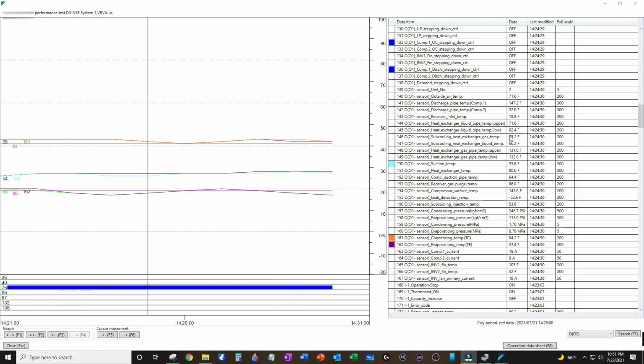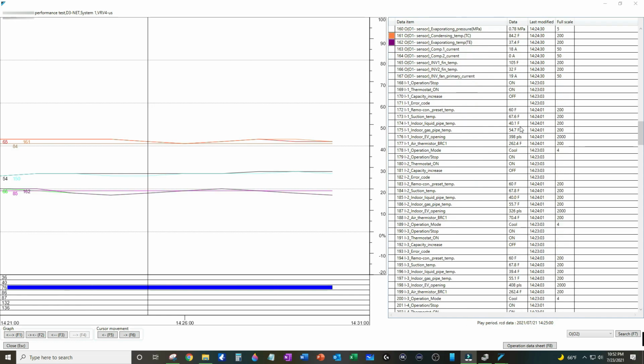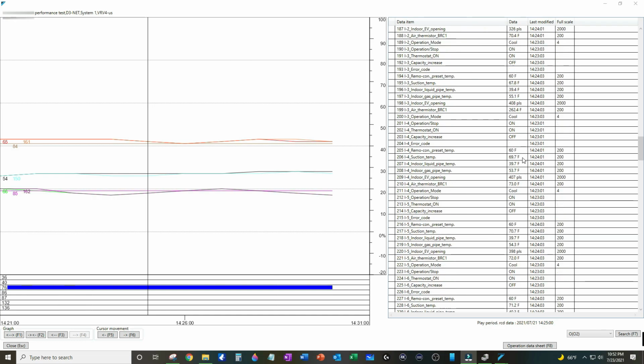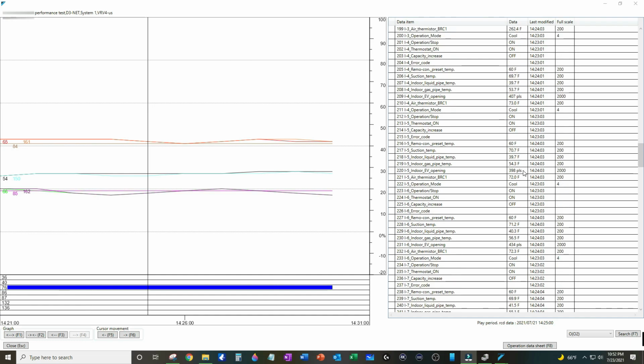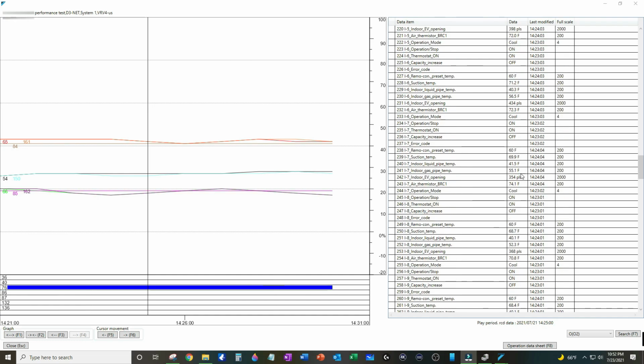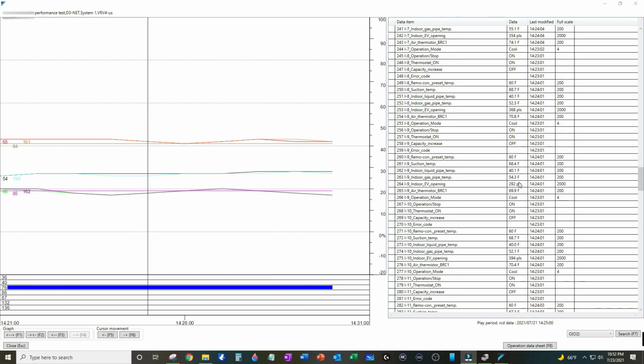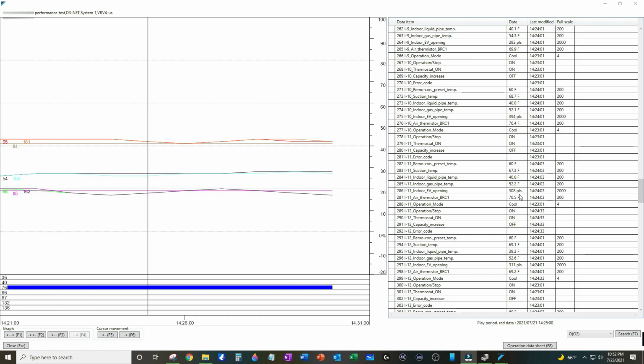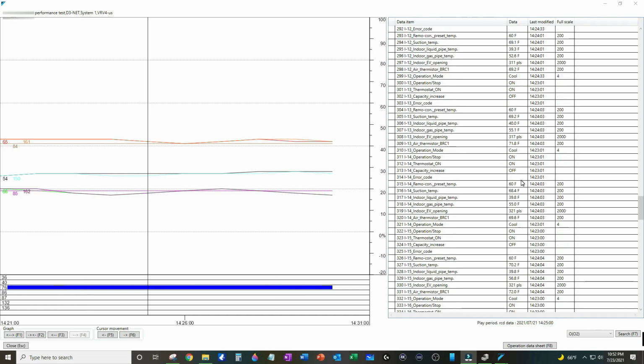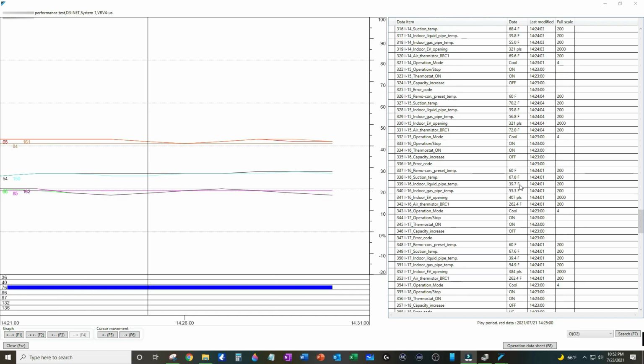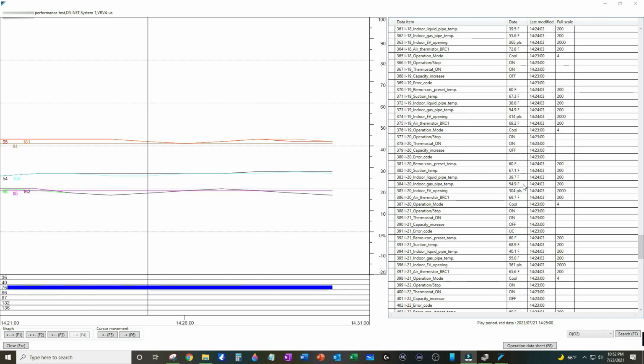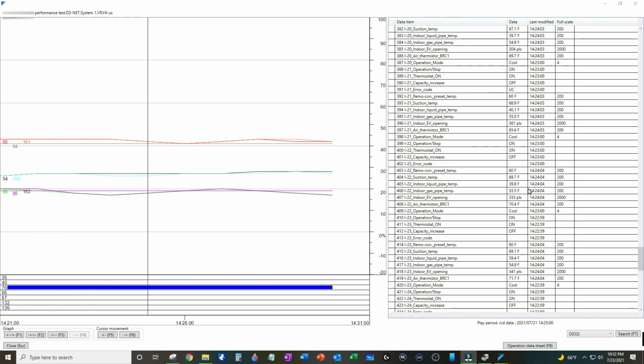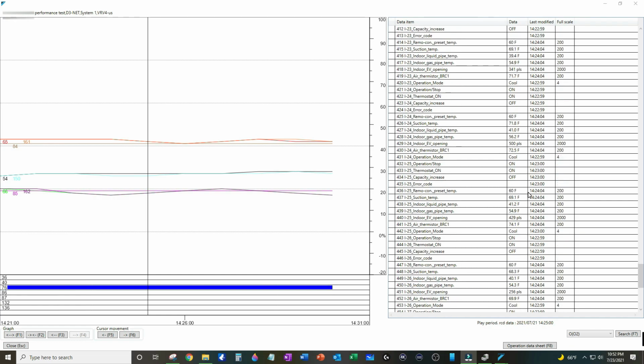The refrigerant will go through the subcooler here to ensure we have proper liquid distribution to the indoor equipment. So far, so good. Indoor units' EEVs will all modulate to control superheat at each indoor unit respectively. So again, I'm going to look at an optimal target of 9 or 10 degrees. Some units running a little low, but nothing too dangerous. Several units just slightly above the 10 degree mark. I'm okay with 15 degrees in most cases and have heard that Daikin is okay with anything up to 27 or 30 degrees. At the end of the day, I think their engineers are more concerned with not enough rather than too much. Too much isn't necessarily the end of the world, but not enough means flooding, and flooding kills compressors. So yeah, I'm fine with 15.